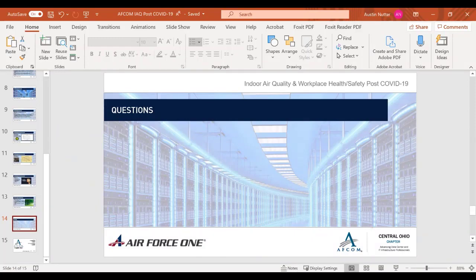Yeah, while he's doing that, I'll give an explanation. We didn't go into the finite details of the piece of equipment, but it's really a flange-mounted device. It has a ballast that creates a higher energy electrical charge. It runs a UV light, which is very low intensity, but directed toward a metal catalyst. It's really cool—the UV light with the metal catalyst and then H2O, water, moisture in the air, creates H2O2.